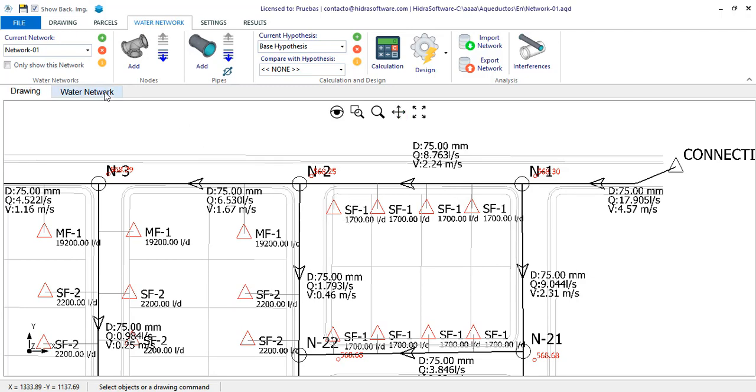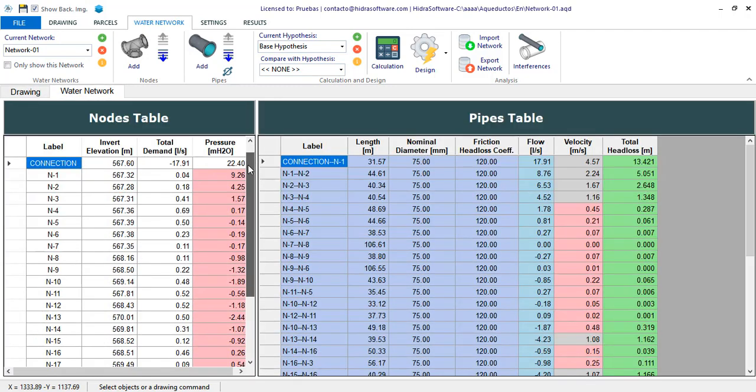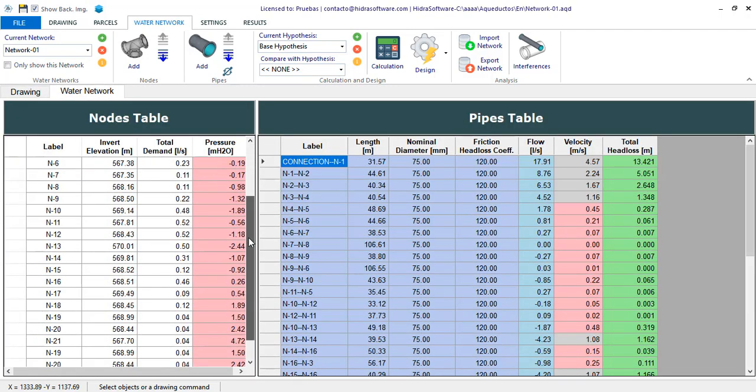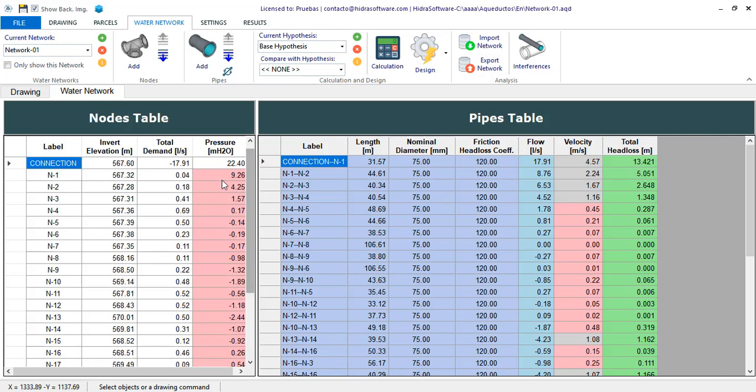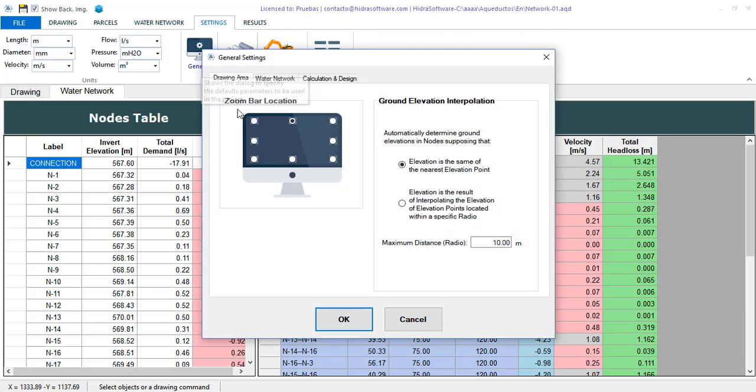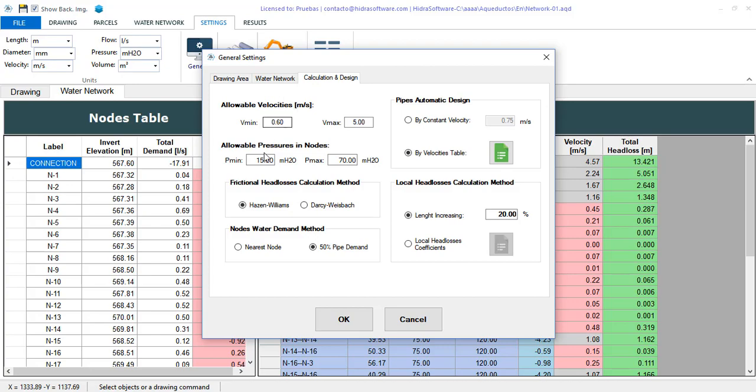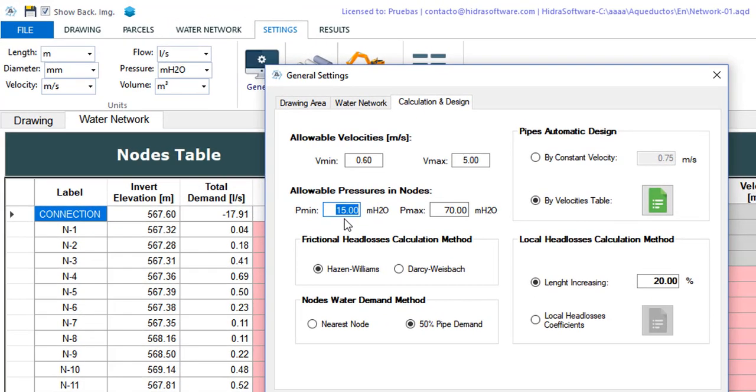If we go to the tables, you will now see that there is a significant number of nodes in which the pressure value is highlighted in red. This is to indicate that its value is below the minimum pressure that we have established in the general settings of the project, which, as you see here, has been set at 15 meters of water column.